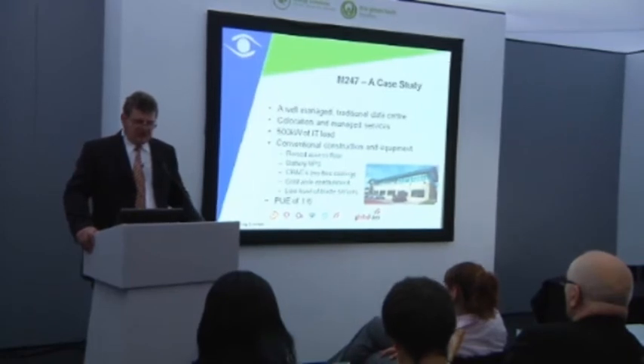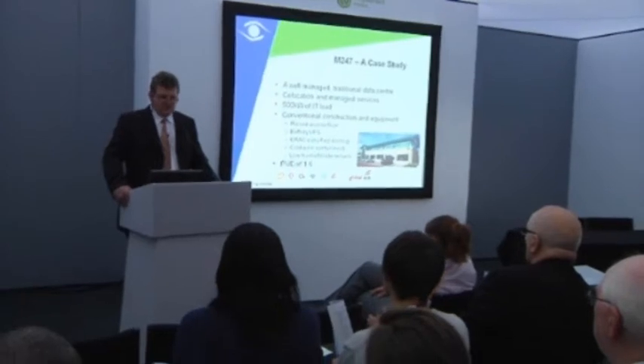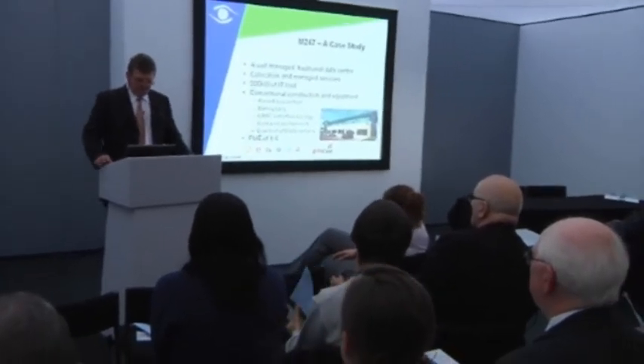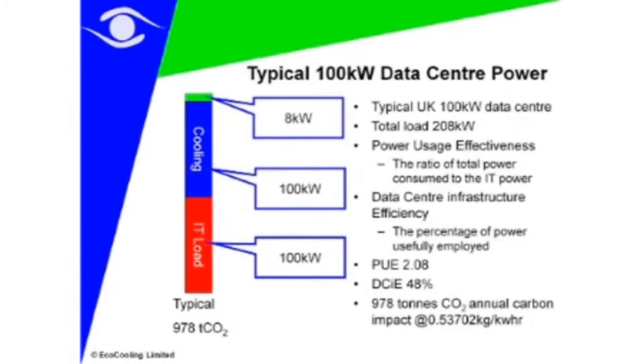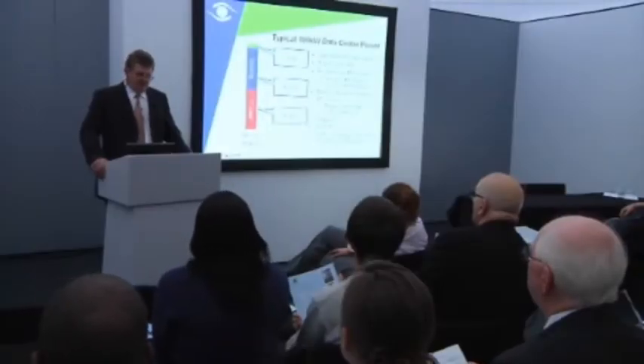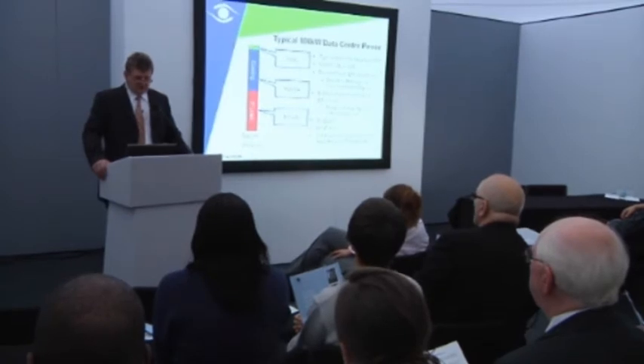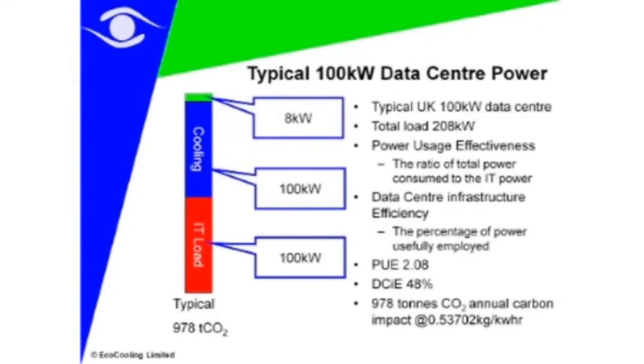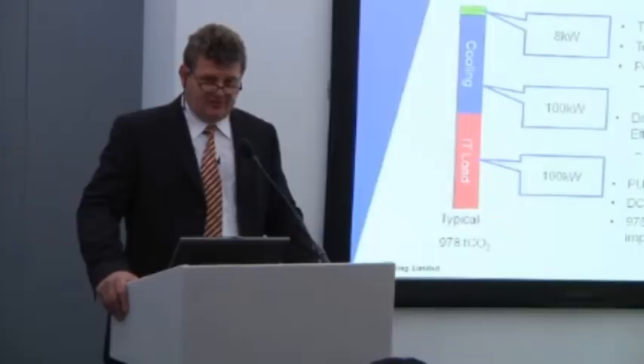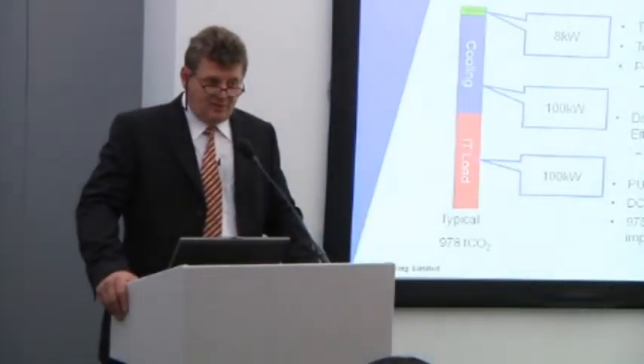They're running at a very good level of efficiency for that type of data center — what we call a PUE, a Power Utilization Effectiveness. PUE is a very important concept: we look at the efficiency of a data center and its energy use by looking at the ratio between the total energy used against what's really useful work done in the IT equipment. Many data centers in Britain run at a PUE of anything up to 2.5.